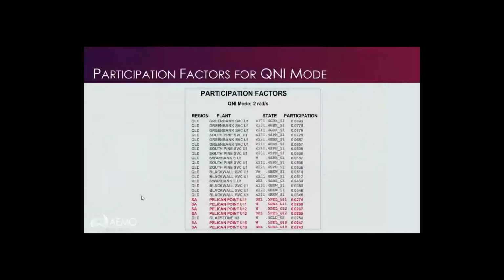To find out the best place to put stabilizing devices, we multiply left and right eigenvectors to get the best measure of each mode's observability and controllability, and this multiplied matrix gives the participation factors. It turns out that the best place to stabilize the QNI mode is to put power oscillation dampers on the SVCs, and the major contributors to QNI damping are Greenbank and Blackwall SVCs, and that's where the PODs were installed.